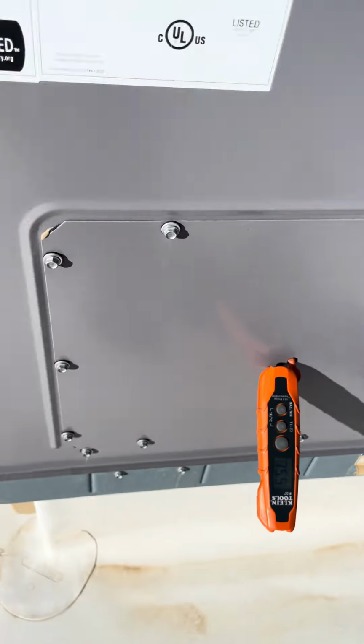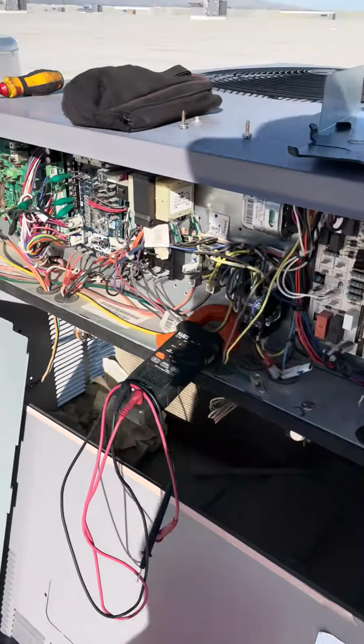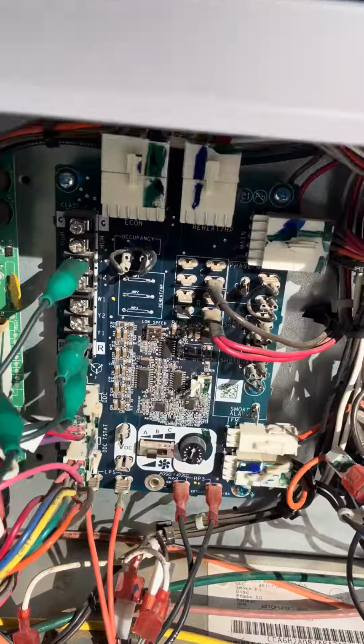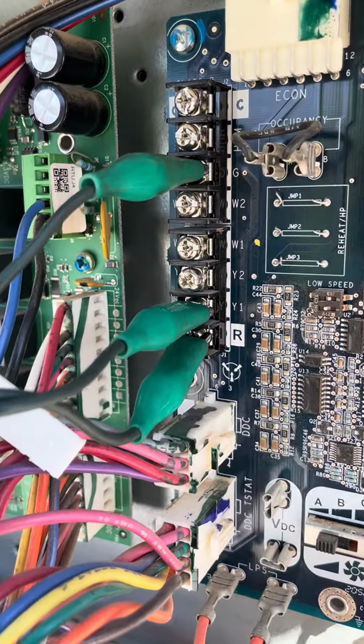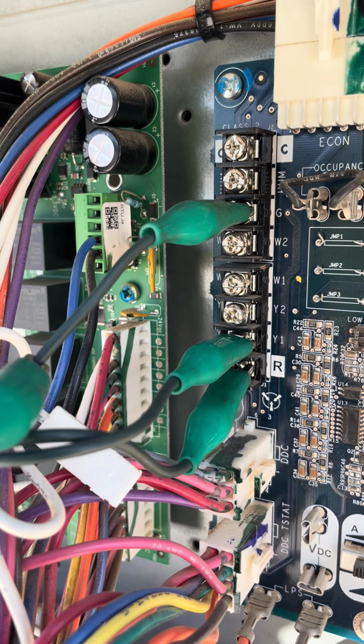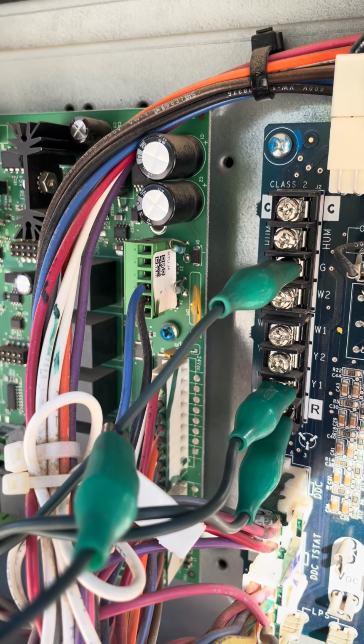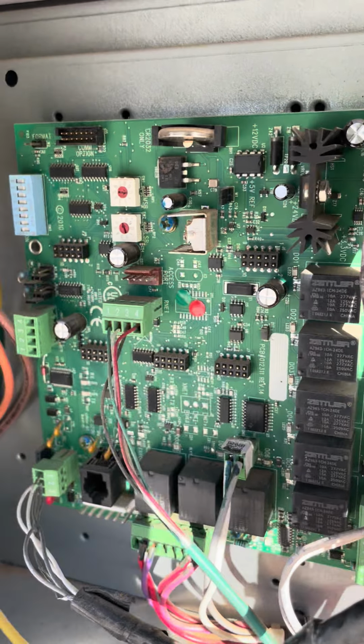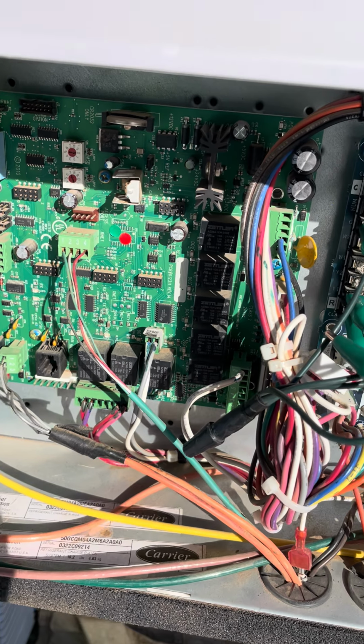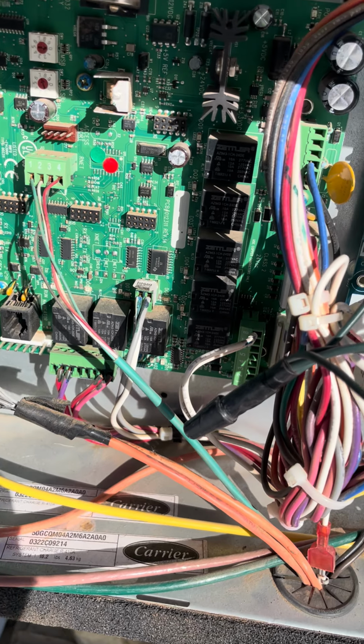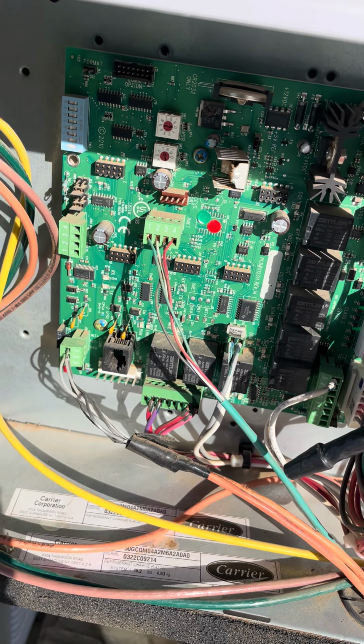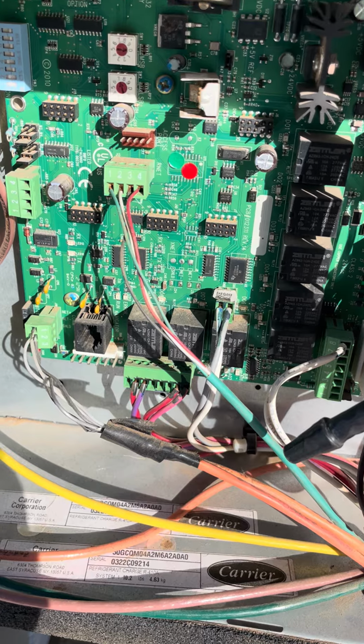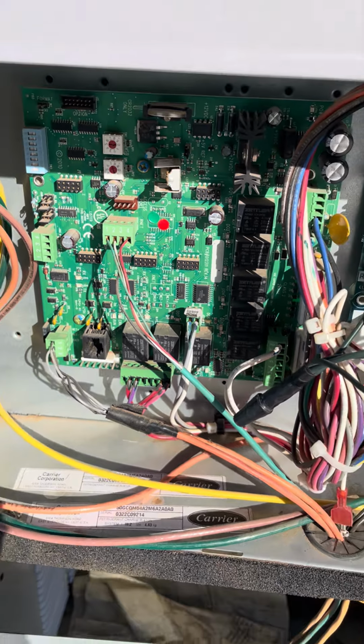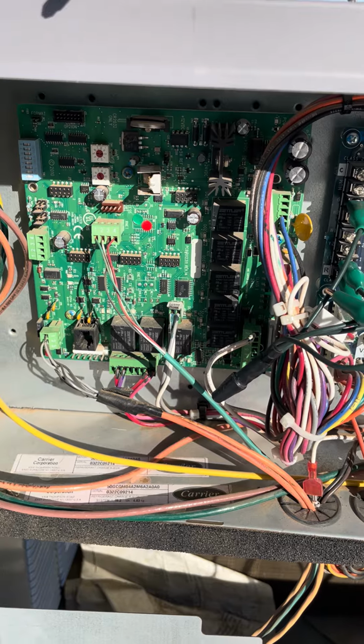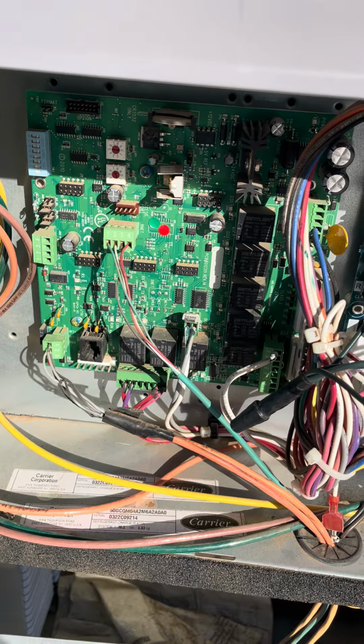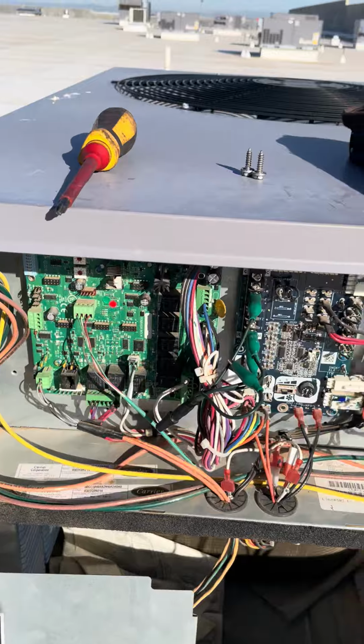Temperature right now is 75, at least it was when I was running. So right now we're jumping out this board. So you have R, Y1, Y2, W1, W2, G, and all of that stuff. This one is the communication board. You have a sensor on the inside measuring the temperature, and then this is the BACnet cable. There's a chain between each unit to an EMS panel, so you can see all the units, see what the unit is doing, if the unit is down and everything. So once you shut down this disconnect, the unit shows offline.